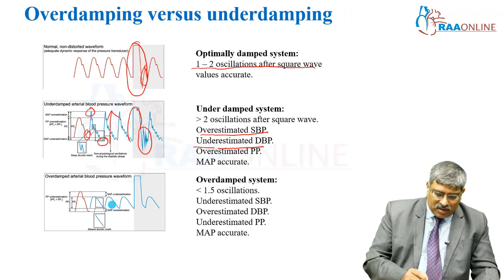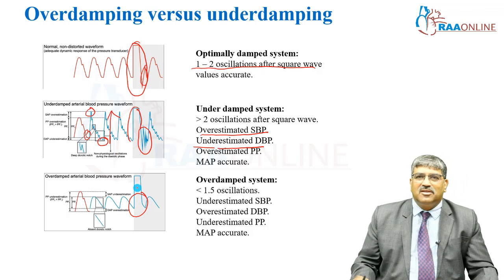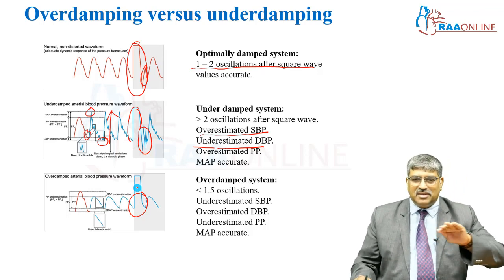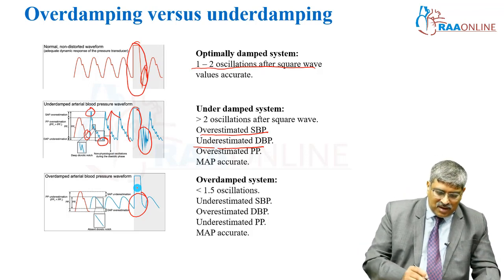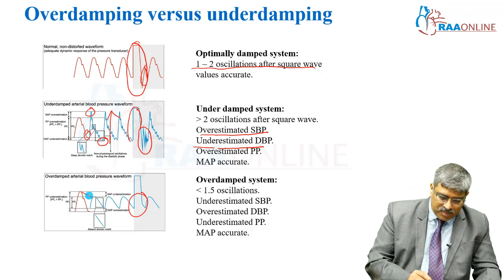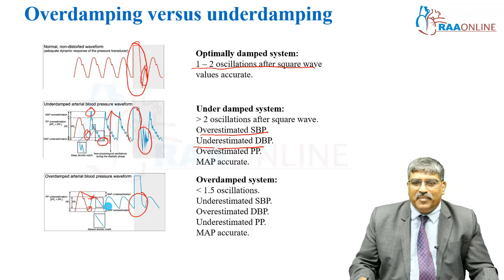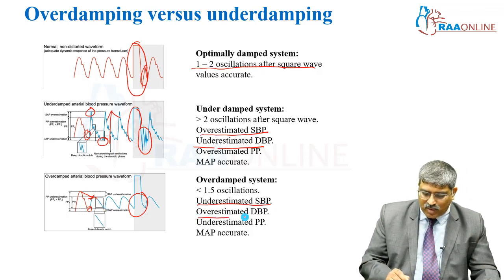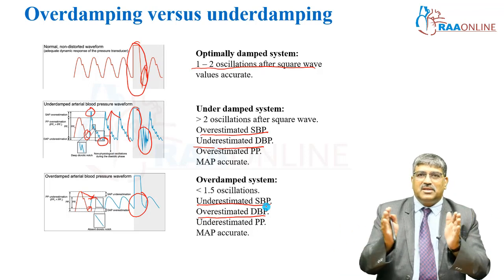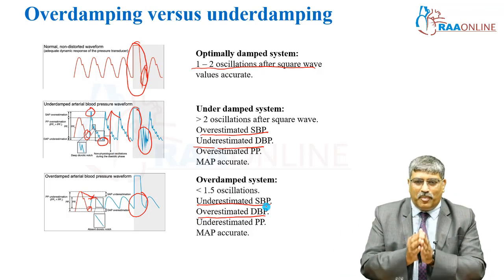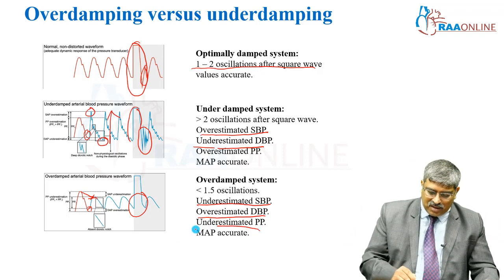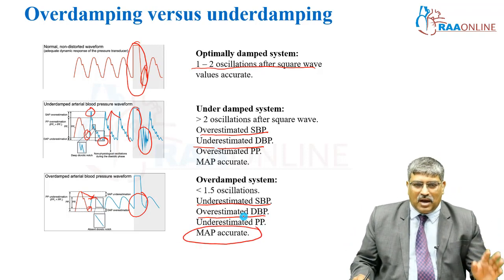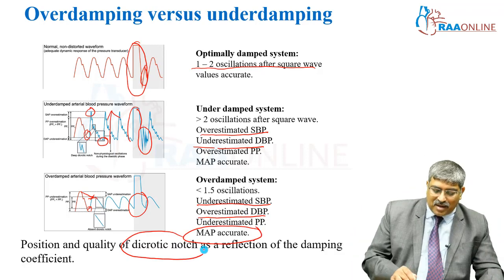Coming to over-damping: when you do the square wave test, there is not much oscillation — less than 1.5 oscillations. Compared to the normal trace, the systolic pressure is low and the diastolic blood pressure is high. So it underestimates systolic blood pressure, overestimates diastolic blood pressure, and underestimates pulse pressure. Mean arterial pressure, however, remains accurate.